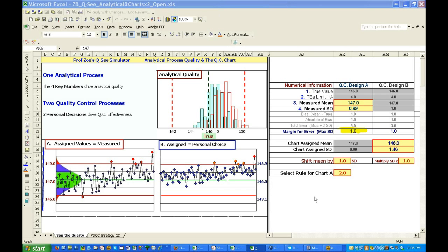Oh, yes. When we have a shift in the mean, we're looking at a systematic error or systematic change. And a lot of times that's when we change lot numbers of reagents, when we calibrate. So anything that affects the specimens that are being analyzed in the same direction will shift the mean. And those are just common instances that occur in the laboratory.